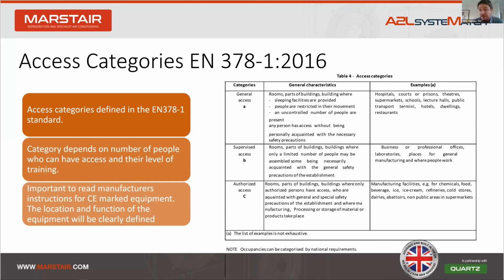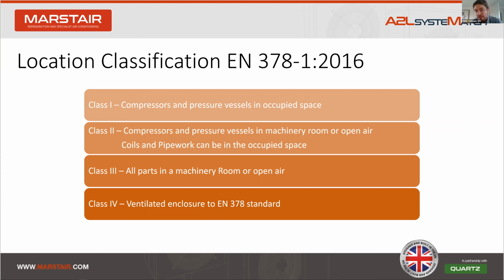The next classification is location classification. Class 1 is compressors and pressure vessels, like receivers, in the occupied space. This could be like a water-cooled condensing unit. Class 2 is compressors and pressure vessels in open air, and coils and pipework in an occupied space. This is a split system. Class 3 is all parts in the machinery room or open air, so this would be equivalent to a chiller. And the final one is class 4, which is ventilated enclosures, which for a cold room you want to try and avoid. So obviously, in terms of cold room split systems, class 2 is where we're at.